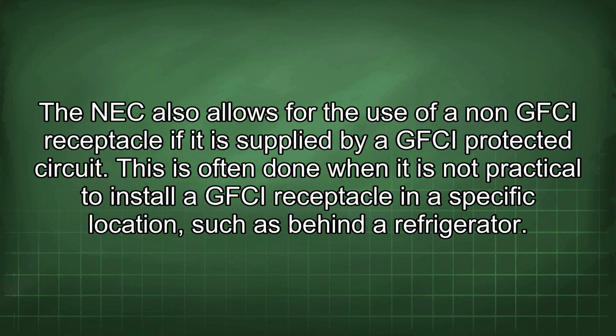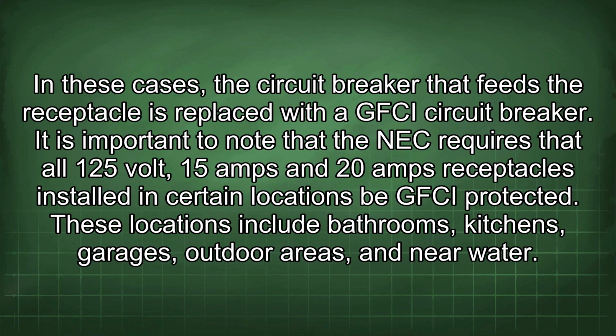The NEC also allows for the use of a non-GFCI receptacle if it is supplied by a GFCI protected circuit. This is often done when it is not practical to install a GFCI receptacle in a specific location, such as behind a refrigerator. In these cases, the circuit breaker that feeds the receptacle is replaced with a GFCI circuit breaker. It is important to note that the NEC requires that all 125 volt, 15 amp and 20 amp receptacles installed in certain locations be GFCI protected. These locations include bathrooms, kitchens, garages, outdoor areas, and near water.